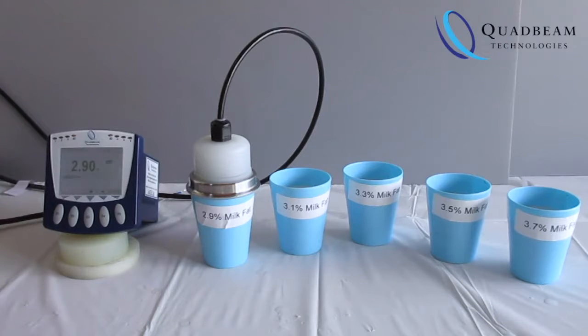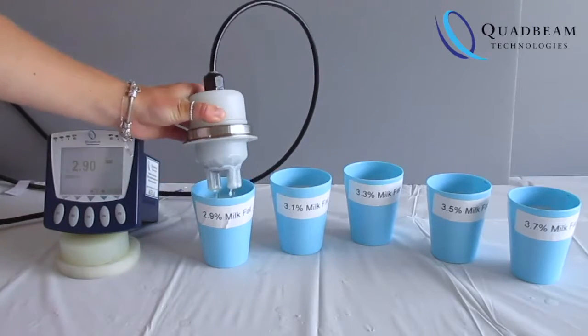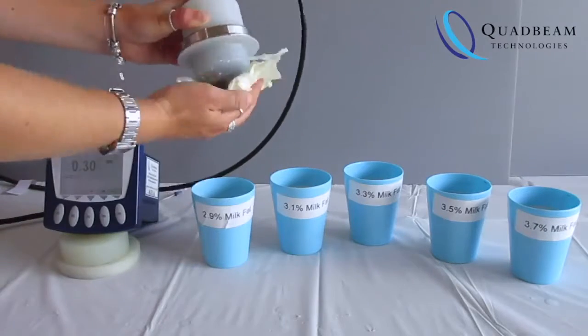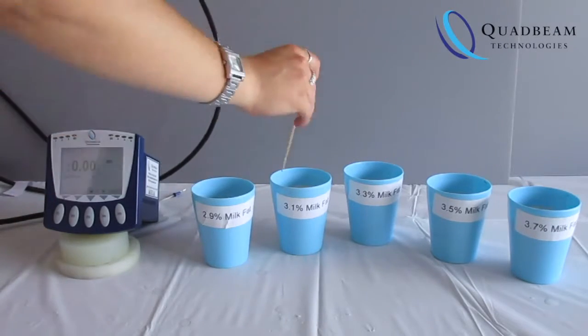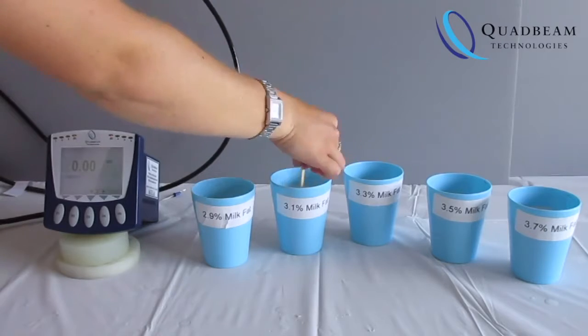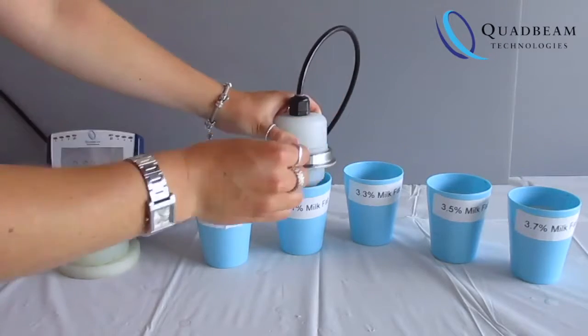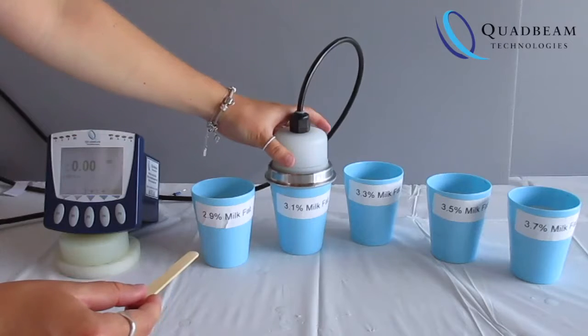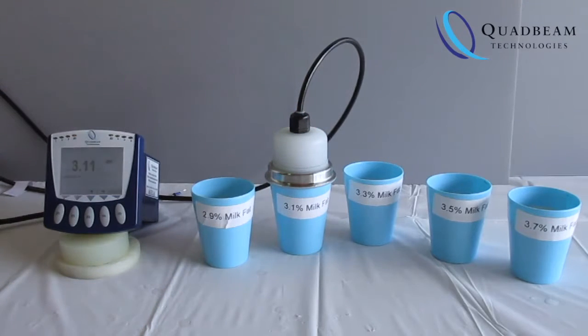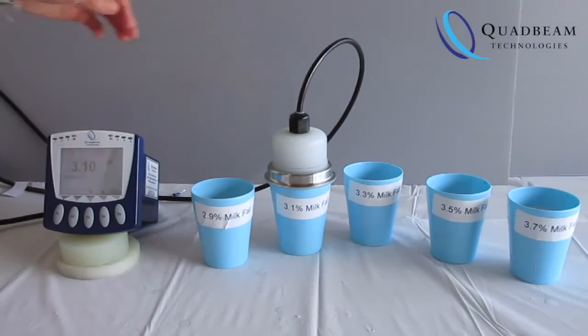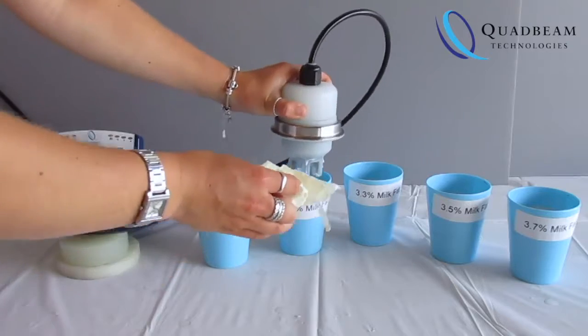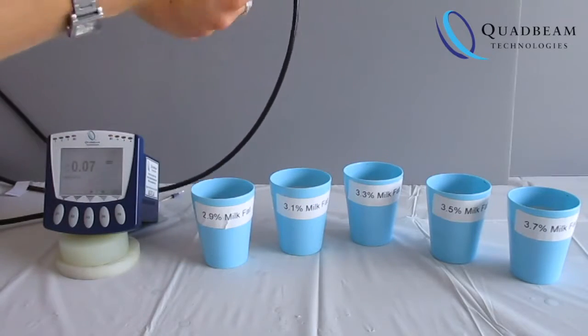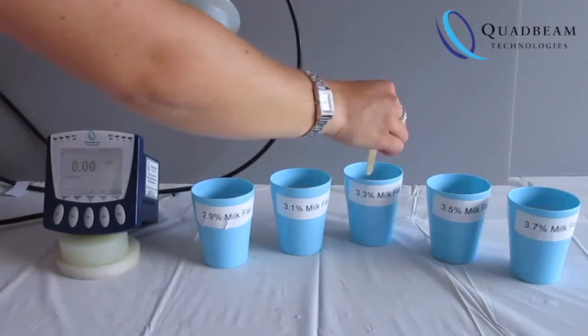Once you've completed all 5 points, do a cross-check to make sure that they're very close. If you do find a difference, it's likely that something's gone a little awry with your setup. Possibly the accuracy of your samples is not quite what it could have been, or you may have some temperature variance or bubbles, or the stirring's not been quite as good as you thought it might have been. Again, the sensor is very, very repeatable. The system's very repeatable, and if you get some strange values, chances are there's some strange inputs.